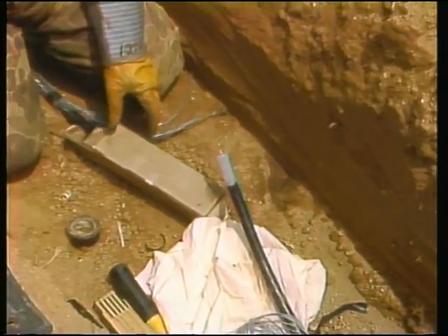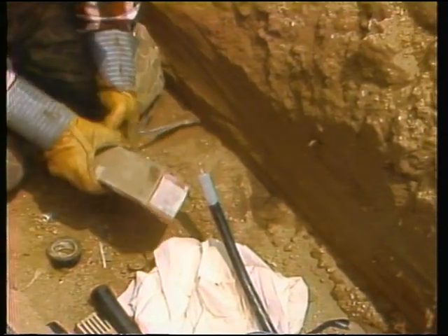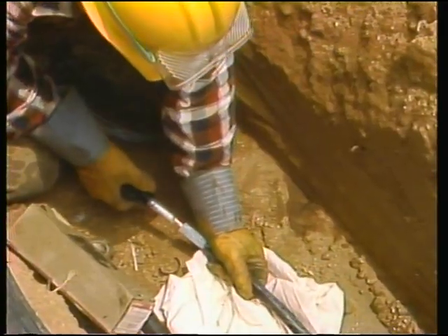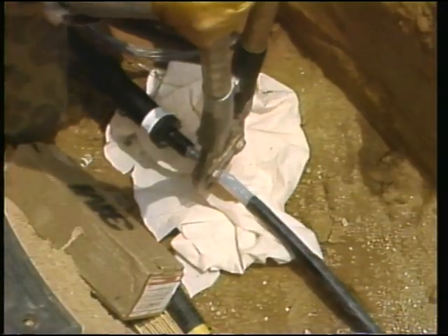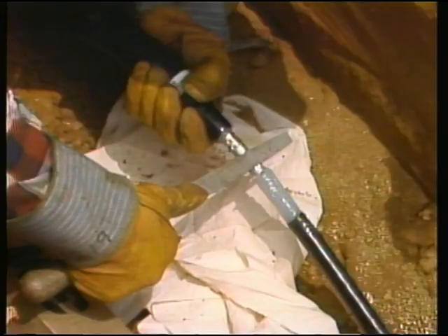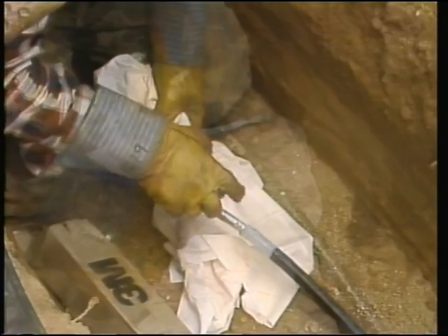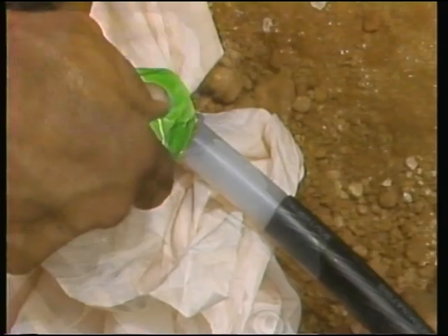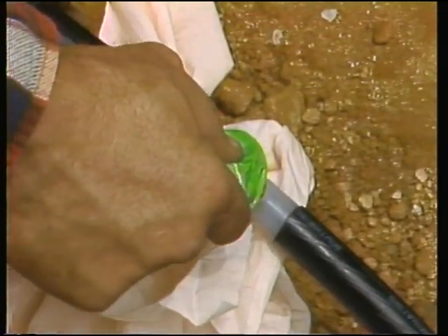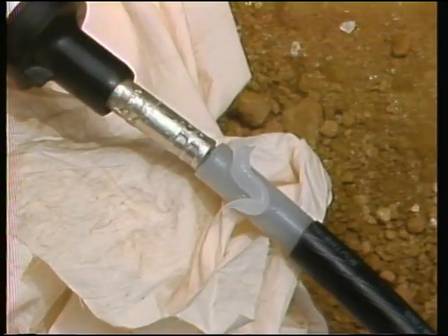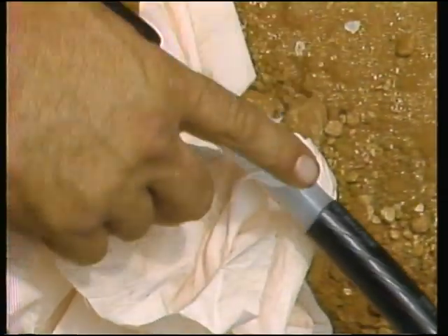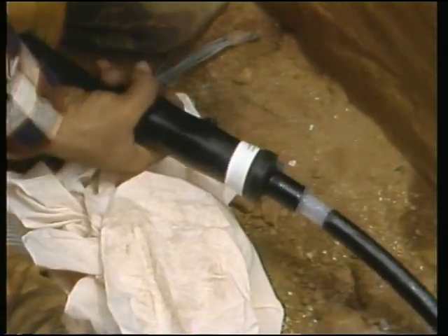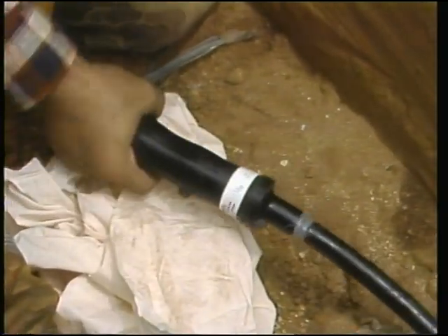He prepares the other cable using the same steps. He then uncovers the first cable, fits the second cable conductor into the compression connector, and makes the compression. Now, to smooth out any rough edges, the connector is filed and then cleaned to remove any metal shavings from the splice area. The workman then takes a small amount of silicone grease and recoats the splice and the cable insulation. Then the splice body can be positioned over the conductor splice according to the splice directions.